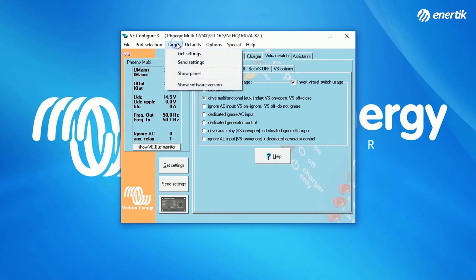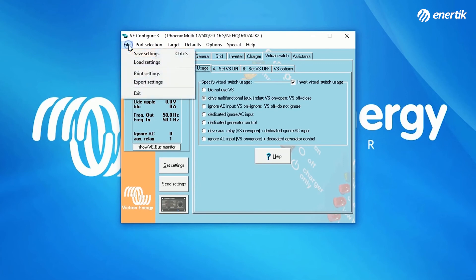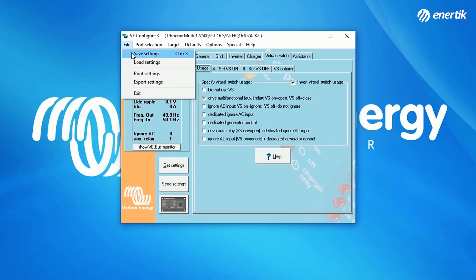If you have made all necessary changes and would like to apply them to the device, select Target in the menu above and Send Settings, or click the Send Settings button in the lower left corner of the VE Configure screen. The configuration will be sent to the device. It is also possible to save your settings by selecting File, Save Settings — a VSC file will be created which you can send by email. When you have received settings via a VSC file, you can load them by selecting File, Load Settings. This was a small introduction to VE Configure. Thank you for watching this video.